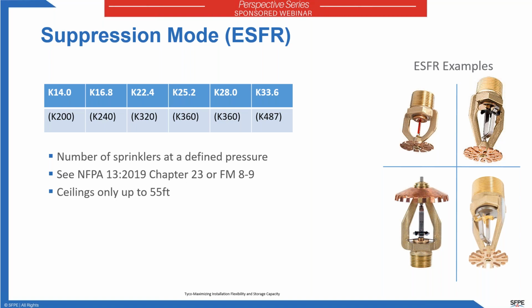Like the CMSA sprinklers, ESFR sprinkler hydraulic designs are based on a number of sprinklers at a defined pressure. You can see the protection schemes in chapter 23 of NFPA 13 2019 or FM 8-9. Now there are protection schemes available using ESFR sprinklers all the way up to a ceiling height of 55 feet, again depending on storage arrangement and commodity classification. So over the past 30 years, there's been a substantial increase in ceiling-only protection schemes through the use of both CMSA and ESFR sprinklers.